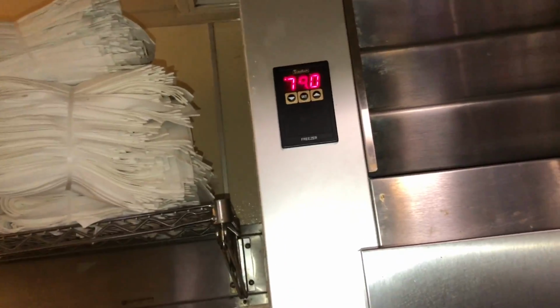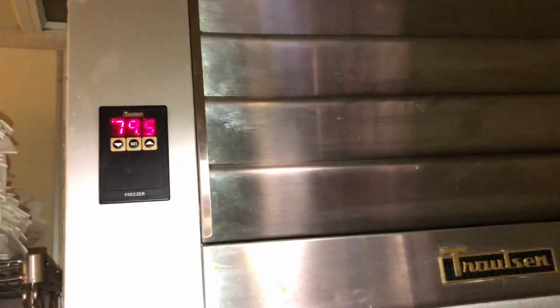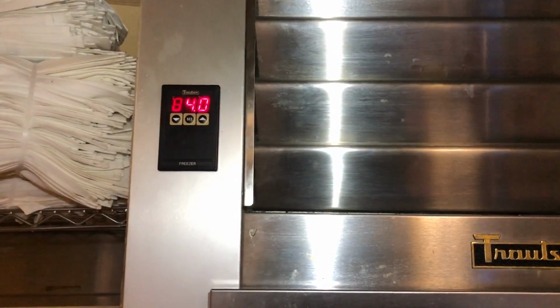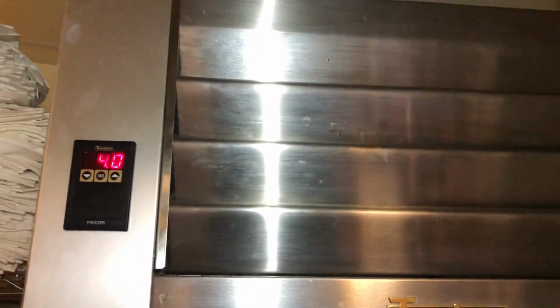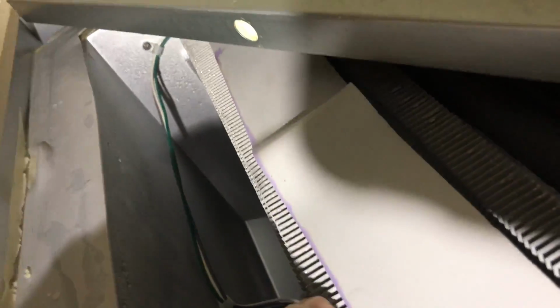79 degrees. Here the compressor and the condensing unit fire right off. So we'll take some covers off and we'll get up there and take a look. It's getting hotter as it's running. It's at 84 now. Let's pop some panels and take a listen around. I had to flip it around to get working on it. So it's running, the condenser fan's running, the condenser's getting hot.